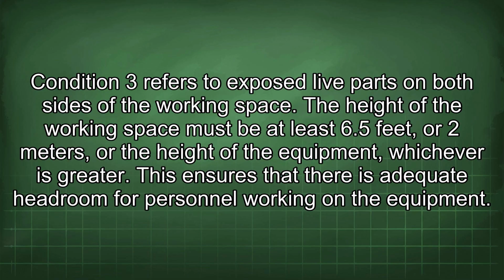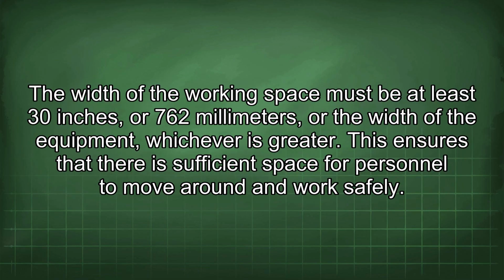The height of the working space must be at least 6.5 feet, or 2 meters, or the height of the equipment, whichever is greater. This ensures that there is adequate headroom for personnel working on the equipment. The width of the working space must be at least 30 inches, or 762 millimeters, or the width of the equipment, whichever is greater. This ensures that there is sufficient space for personnel to move around and work safely.